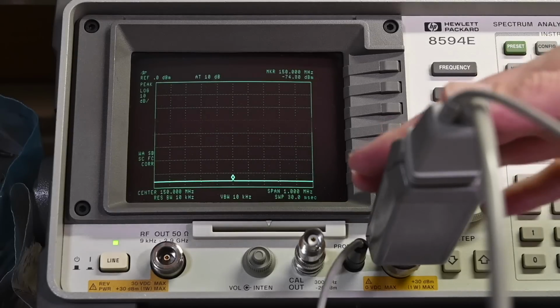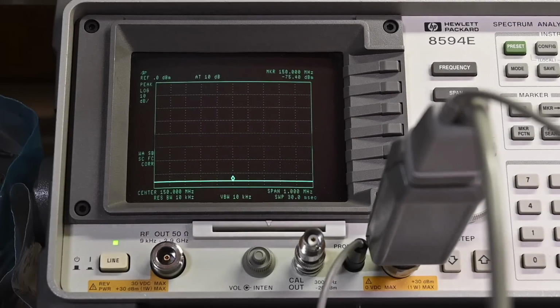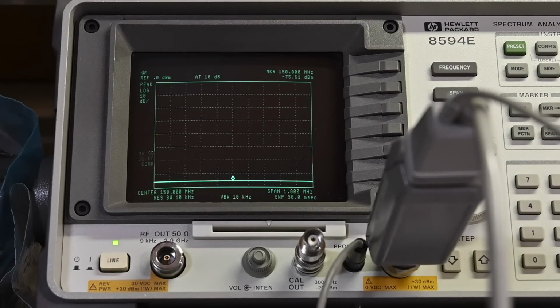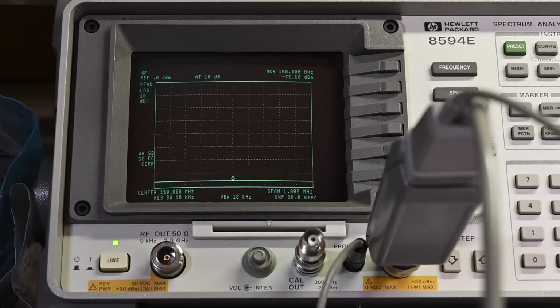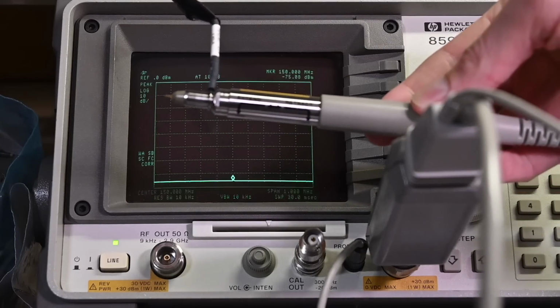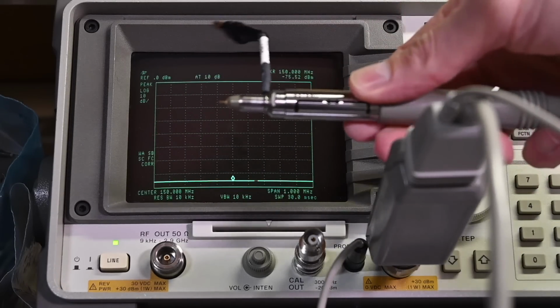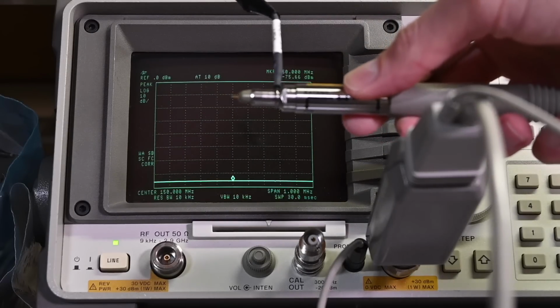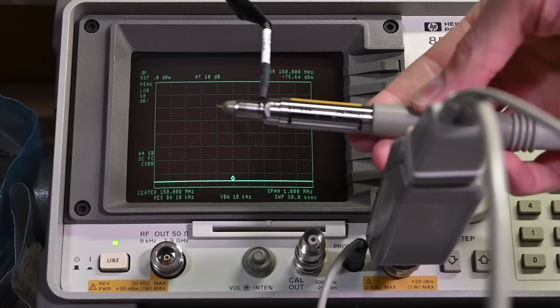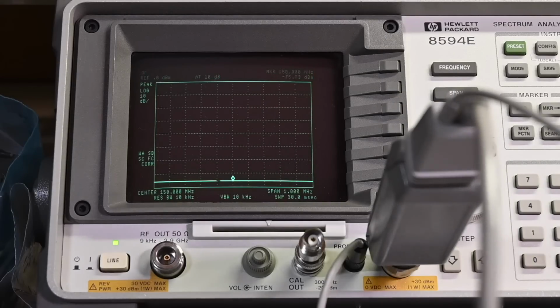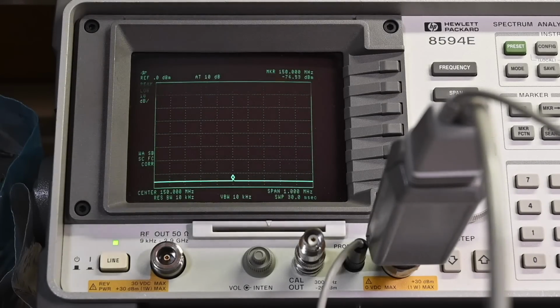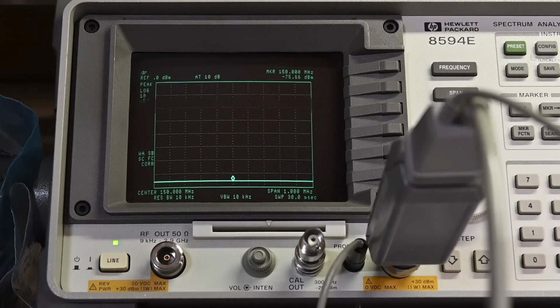Now this piece right here that's sort of out of focus is part of the active probe that I'm using. It's a Hewlett-Packard model 85024A, and again, here's the probe tip right there. The tip actually gets warm. There's active circuitry in the end right here. It's a very high impedance input. It works very well. It's necessary when you're reading on RF circuits because you don't want to interfere with the circuit. You can't just probe in with a low impedance type probe. This probe doesn't have an attenuator on the end right now, so it's just a 1-to-1 reading.